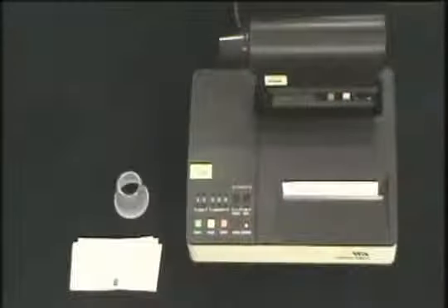The spirometer. Today we're going to be using a Welch Allyn. It's an older model, but it records on paper someone's pulmonary function. We use this mostly in occupational medicine for surveillance for people who are around chemicals or other substances that might affect their breathing, to make sure that they're not being hurt by their job. This machine has important functions, a mouthpiece, which you want to make sure is clean.